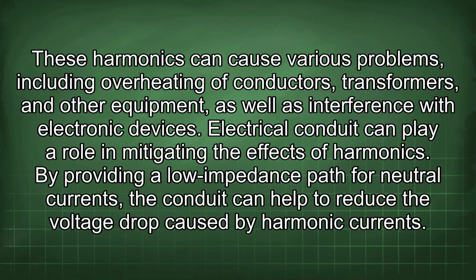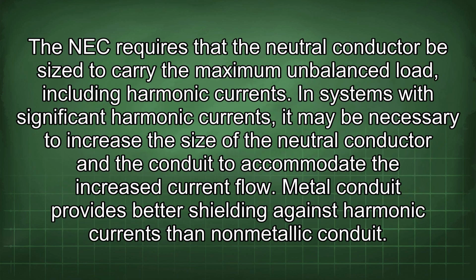By providing a low impedance path for neutral currents, the conduit can help to reduce the voltage drop caused by harmonic currents. The NEC requires that the neutral conductor be sized to carry the maximum unbalanced load, including harmonic currents. In systems with significant harmonic currents, it may be necessary to increase the size of the neutral conductor and the conduit to accommodate the increased current flow.